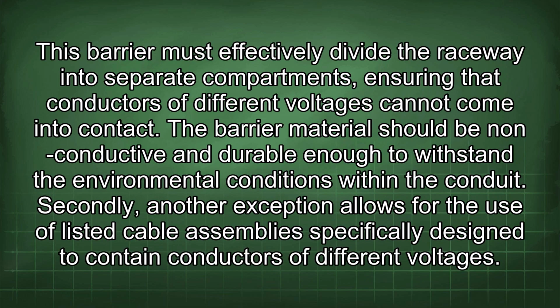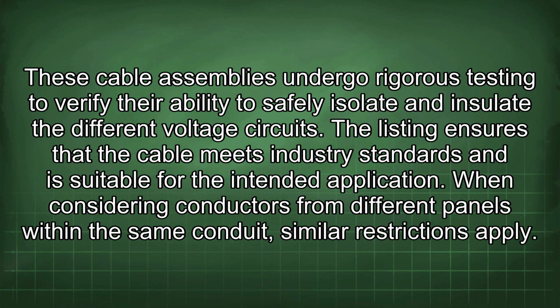This barrier must effectively divide the raceway into separate compartments, ensuring that conductors of different voltages cannot come into contact. The barrier material should be non-conductive and durable enough to withstand the environmental conditions within the conduit. Secondly, another exception allows for the use of listed cable assemblies specifically designed to contain conductors of different voltages. These cable assemblies undergo rigorous testing to verify their ability to safely isolate and insulate the different voltage circuits. The listing ensures that the cable meets industry standards and is suitable for the intended application.